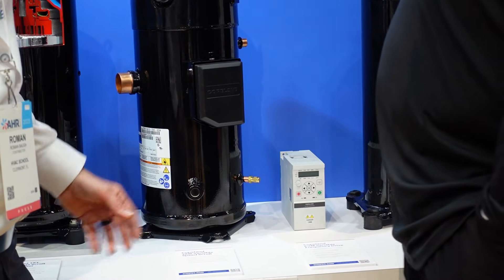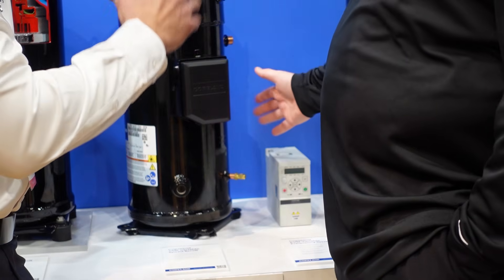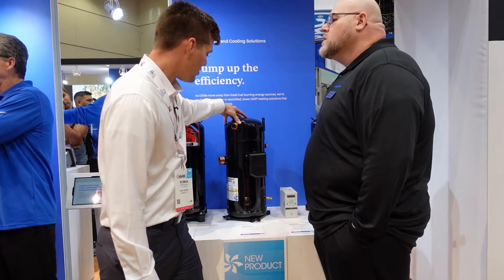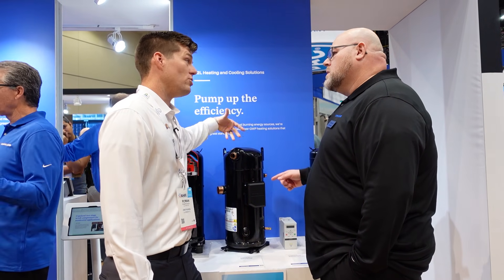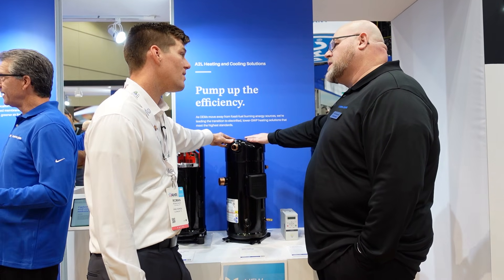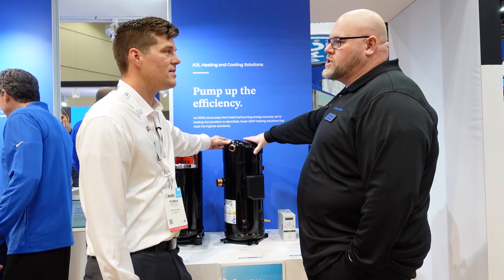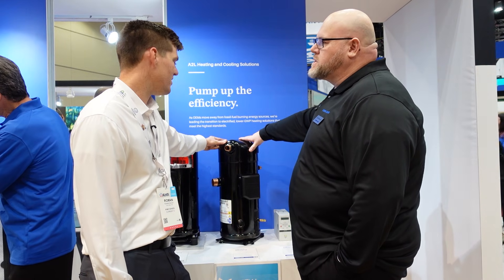It's not that crazy big either. People might expect a large VFD, but this one pairs nicely with the compressor. With vapor injection and the capacity changes it enables, you can now get up to 20% more capacity and about 10% energy savings using this technology.